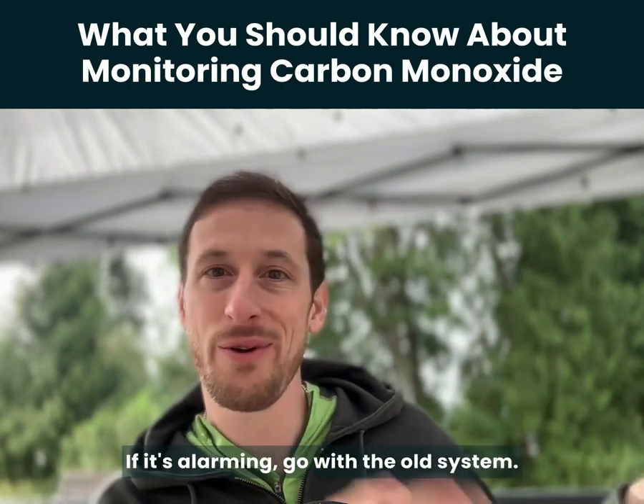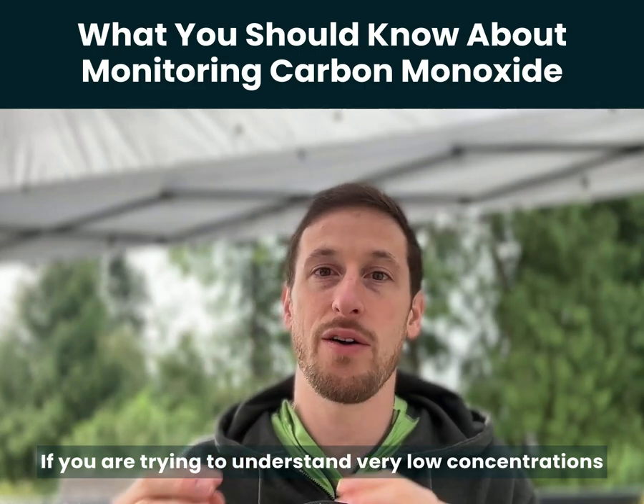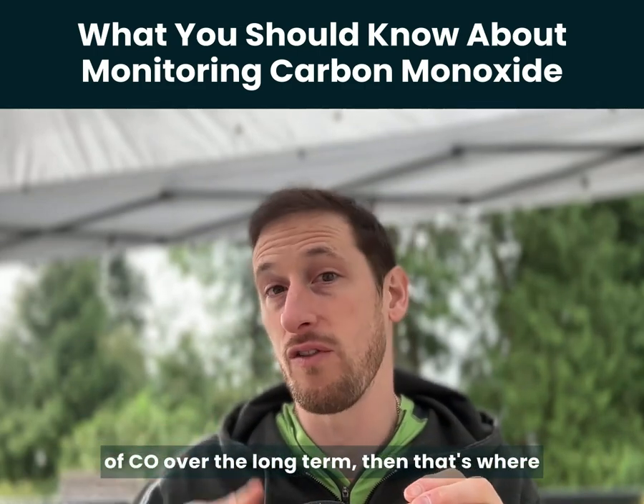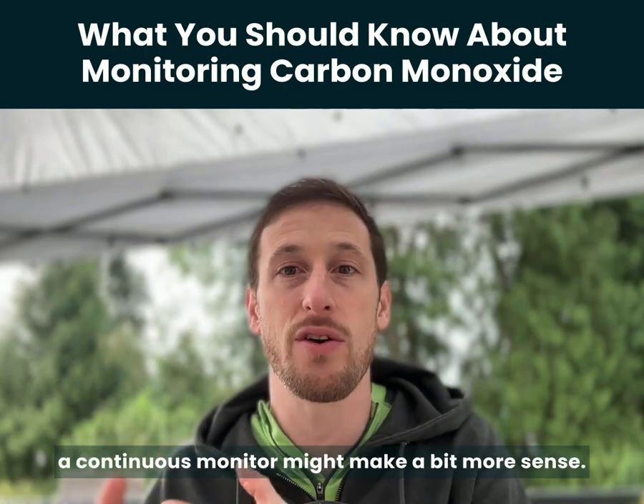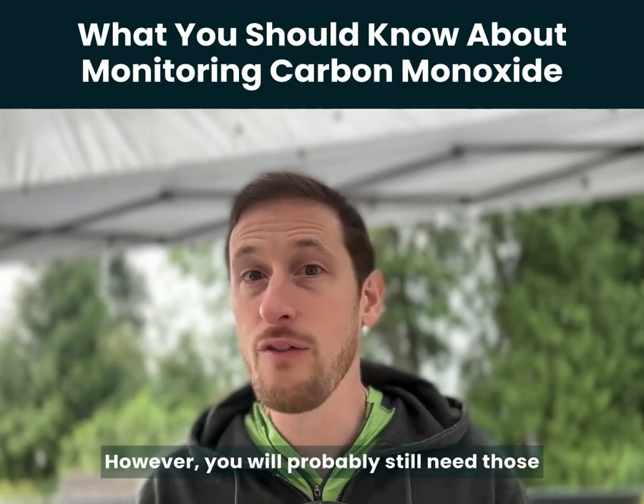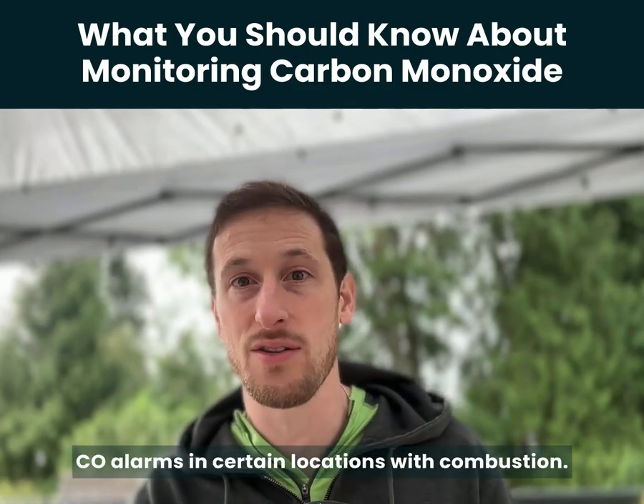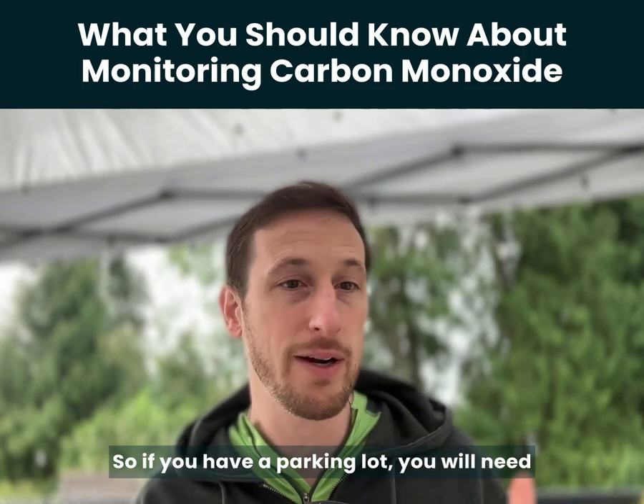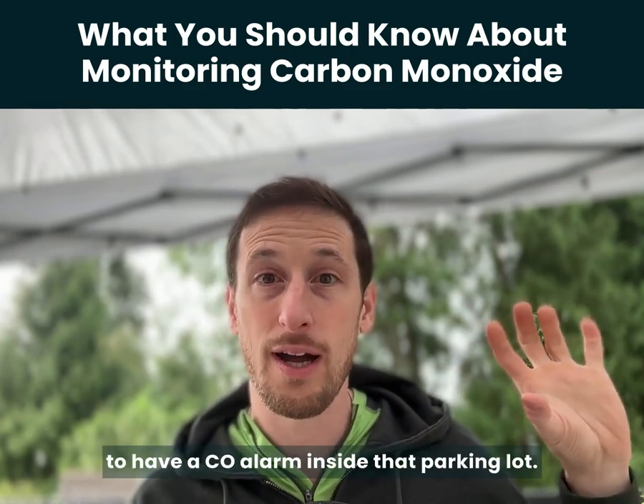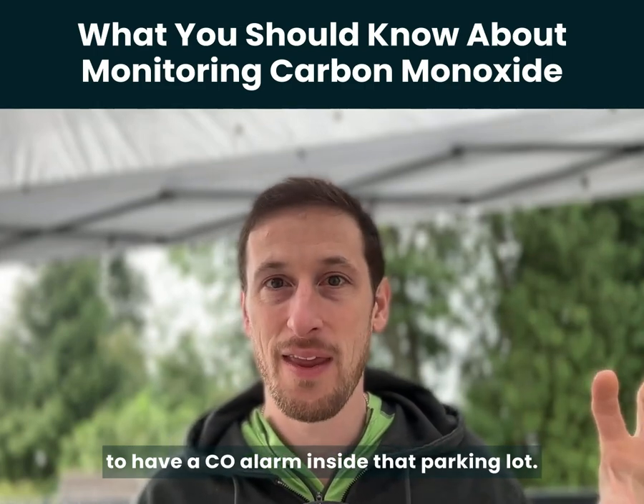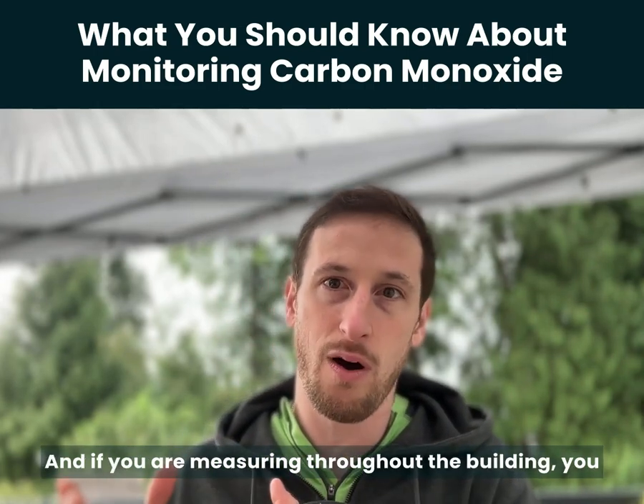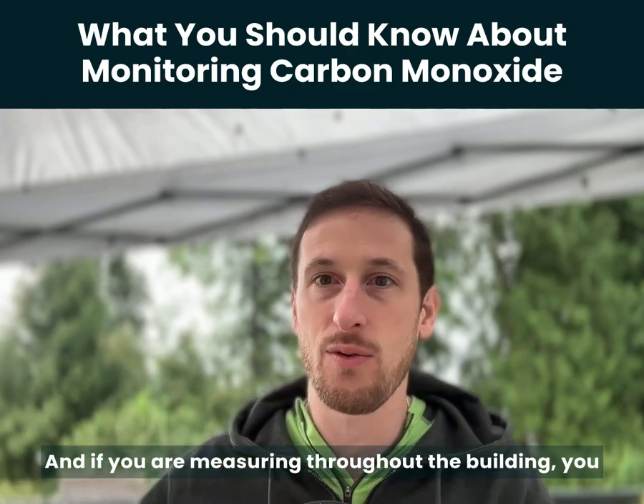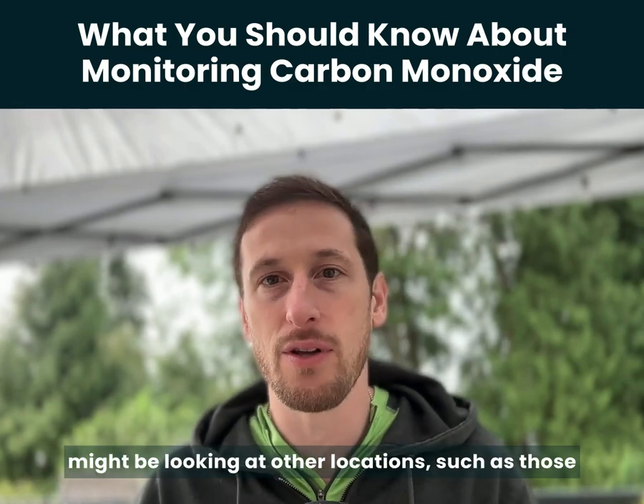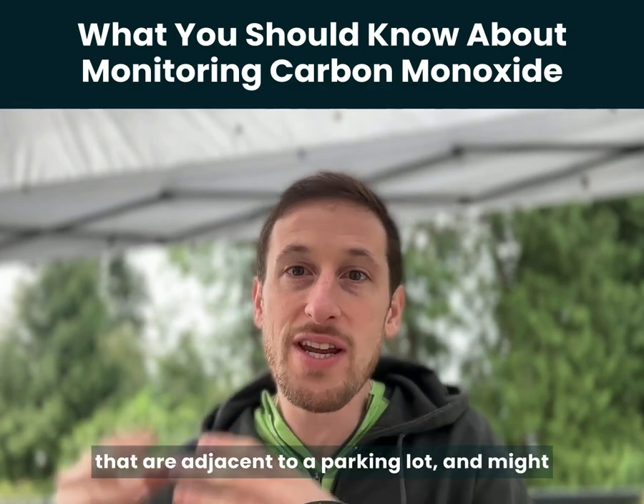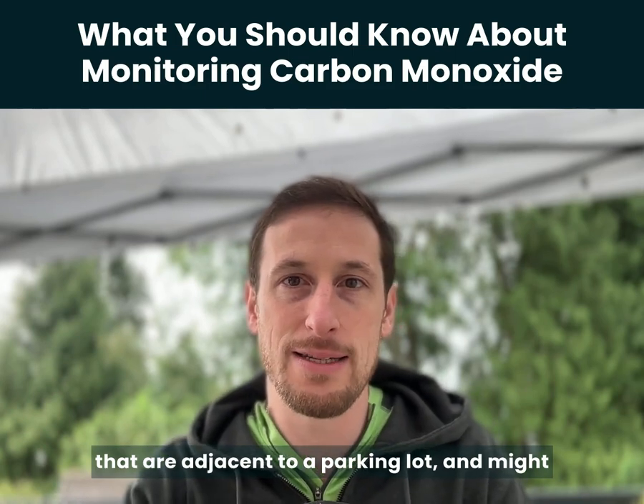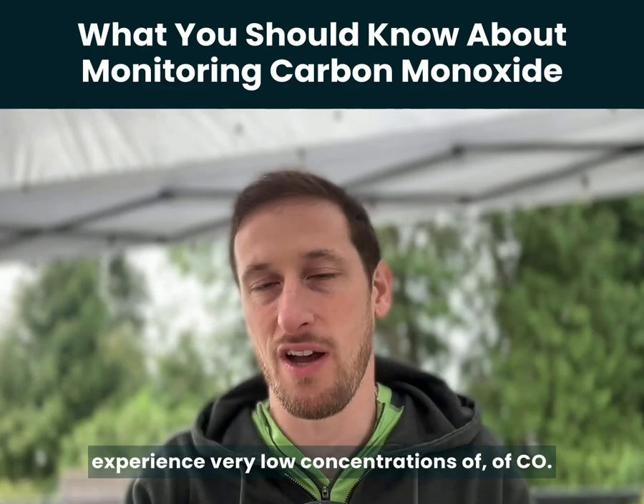If it's alarming, go with the old system. If you are trying to understand very low concentrations of CO over the long term, then that's where a continuous monitor might make a bit more sense. However, you will probably still need those CO alarms in certain locations with combustion. So if you have a parking lot, you will need to have a CO alarm inside that parking lot. And if you are measuring throughout the building, you might be looking at other locations, such as those that are adjacent to a parking lot, and might experience very low concentrations of CO.